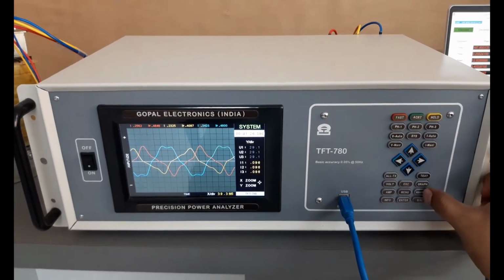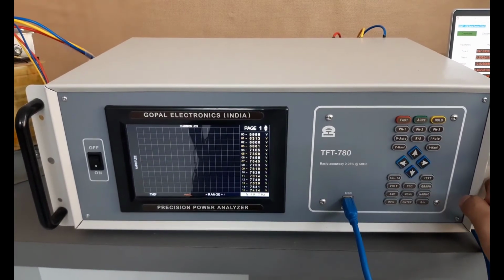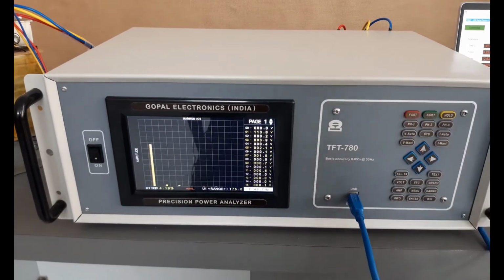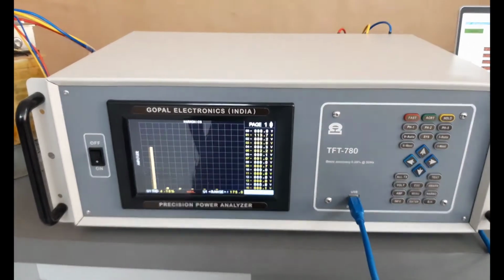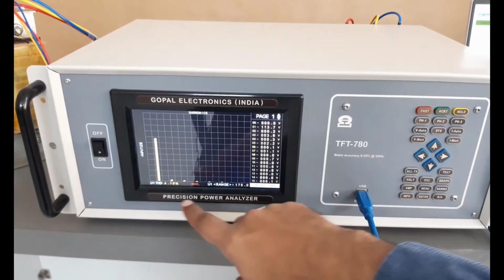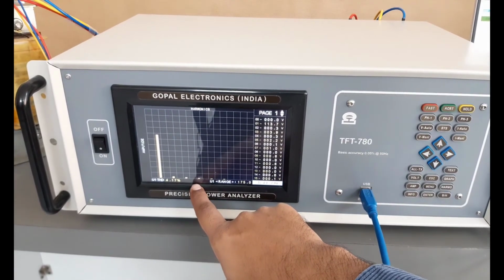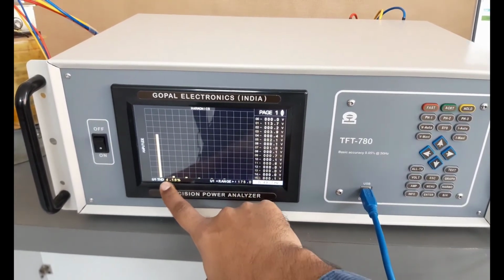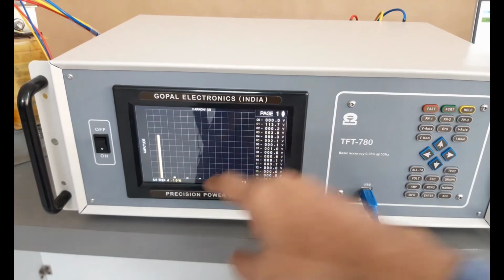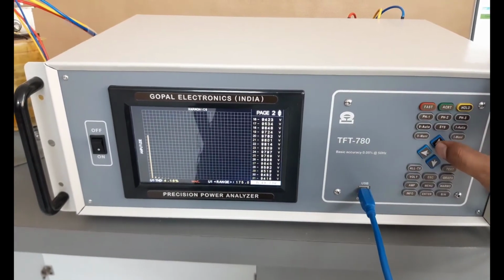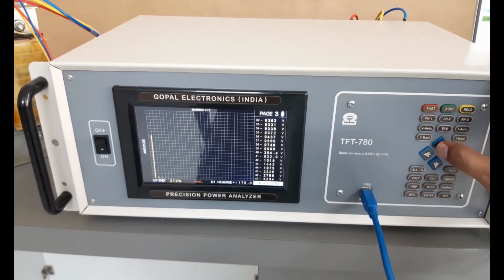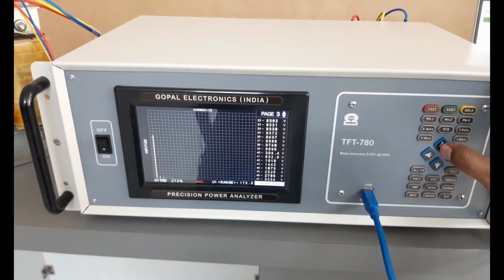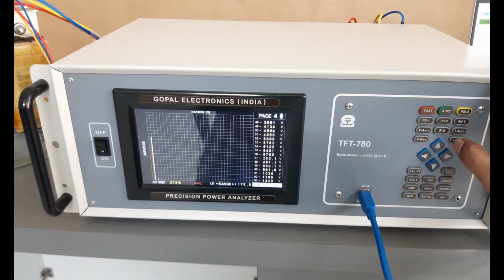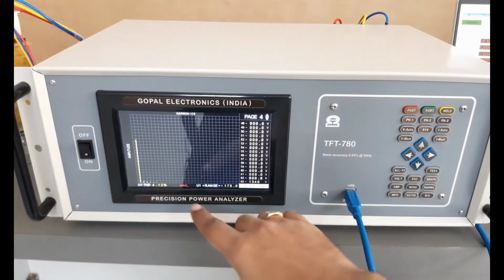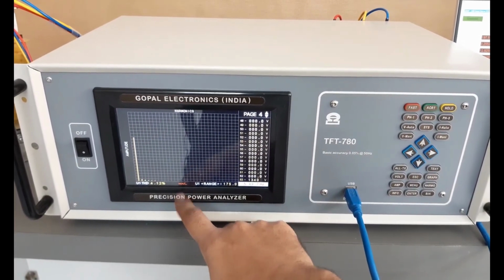Now let's check harmonics mode. You need to wait until this wait go. This is THD value of phase 1 voltage. Now you can press up key to scroll the pages up to 64th harmonics. You can take readings after this wait go.